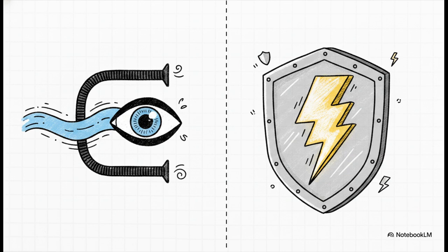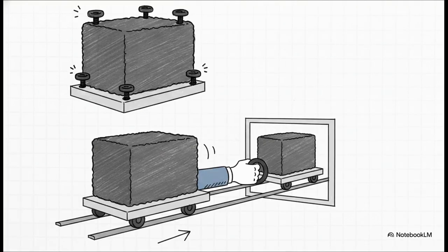Just to quickly set our bearings based on where we left off, we've already locked down the current side of the equation. We saw how current transformers and Rogowski coils act as the eyes of the protection relays by scaling down massive amps into tiny, easily measurable signals. With that covered, our focus shifts entirely to the other half of the power equation. Let's tackle voltage and look at the actual hardware designed to safely capture it. Well, the traditional solution to this voltage problem is the conventional voltage transformer, or VT.